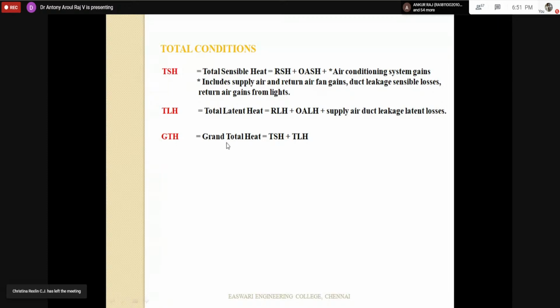So why do we go for the effective sensible heat or effective sensible heat factor calculation? That is not for energy requirement or energy simulation. That is for designing. For designing, you require a fan. We require a fan for the air handling unit, and that fan should have sufficient capacity. Yesterday we saw that if it is near ADP, a lesser volume is sufficient.